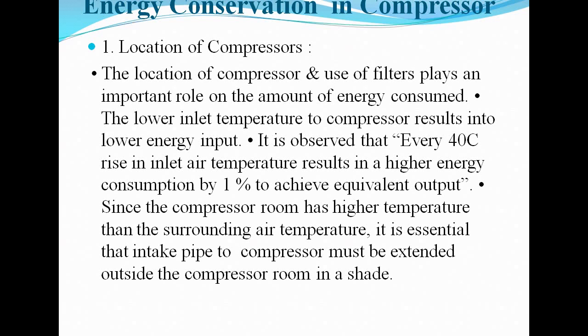This leads to an increase in inlet temperature, and this also leads to an increase in energy consumption. So for that reason, the inlet pipe to the compressor must be extended outside the compressor room in a shade, so that the air will circulate to the inlet pipe and the temperature of the inlet air will be kept minimum or lower.